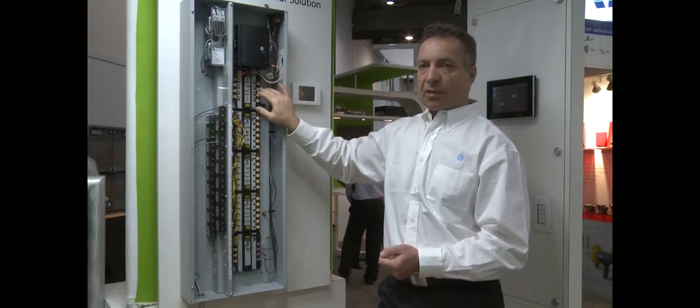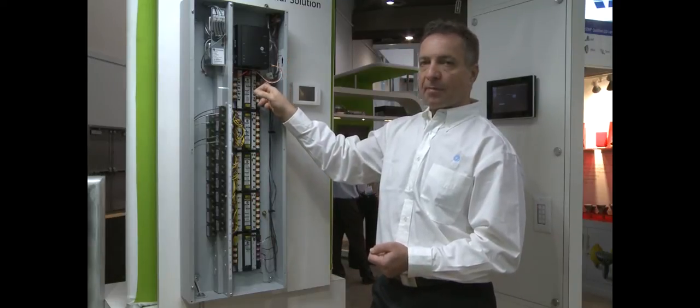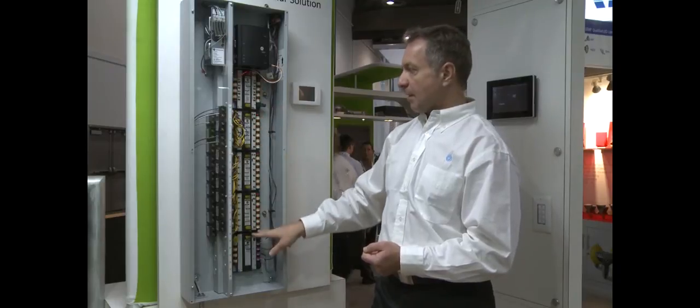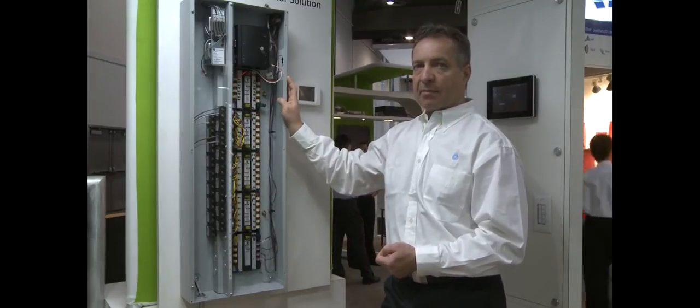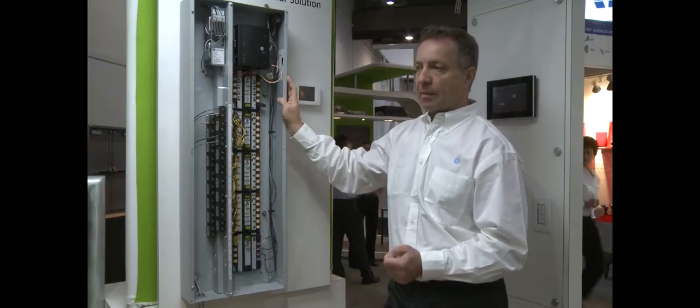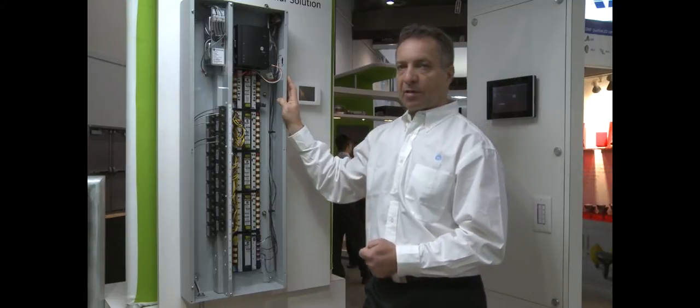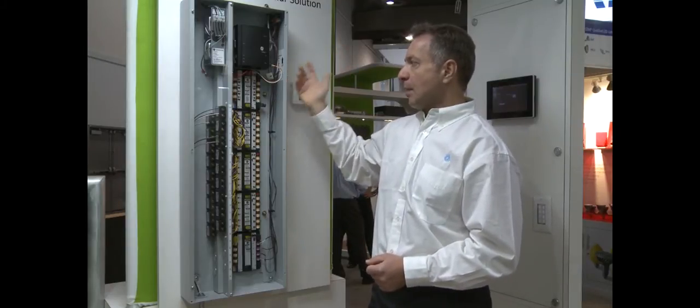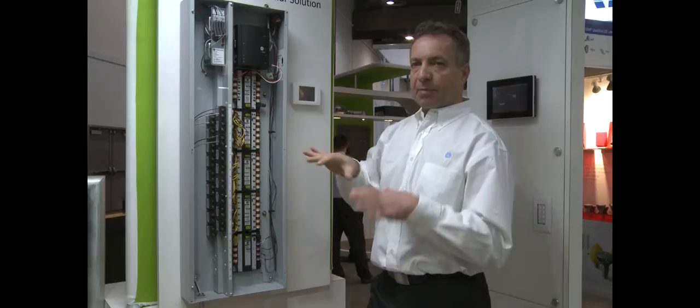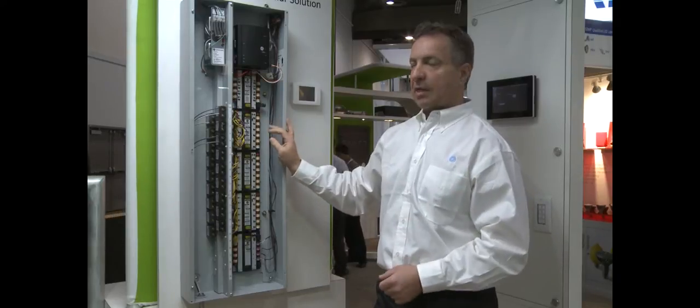Multiple panels can be connected together using a CAT5 connection. Communication between these devices and panels will be using CAN bus, which is a protocol coming from auto industry, a very fast communication protocol. So up to 99 of these devices spread in different panels can be connected to one network.